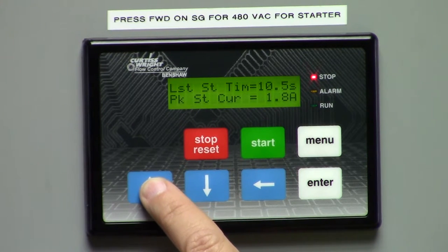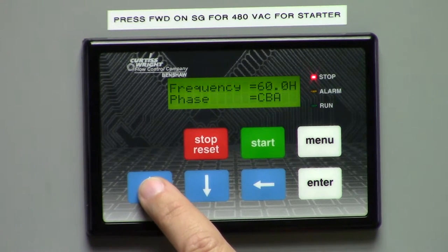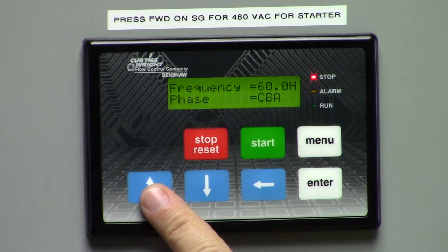Also, as you go up through, it'll tell you the last start time, meaning how long it took to start and come up to full speed, and the peak current that it drew during that start. It shows you the frequency. It also tells you the order of the phase that's feeding the starter.